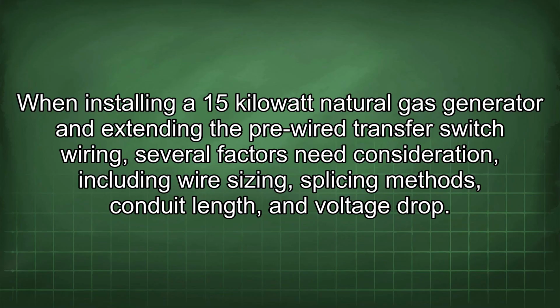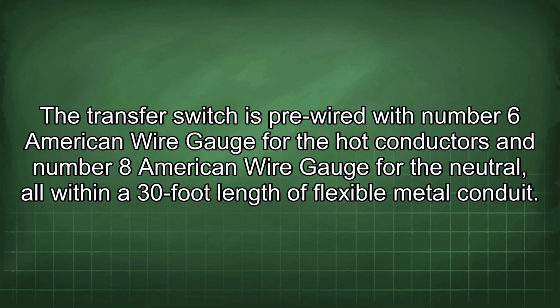When installing a 15 kilowatt natural gas generator and extending the pre-wired transfer switch wiring, several factors need consideration, including wire sizing, splicing methods, conduit length, and voltage drop. The transfer switch is pre-wired with number 6 American wire gauge for the hot conductors and number 8 American wire gauge for the neutral, all within a 30-foot length of flexible metal conduit.